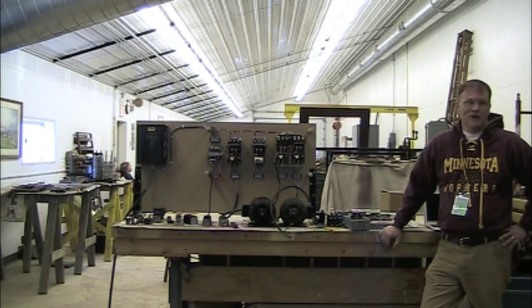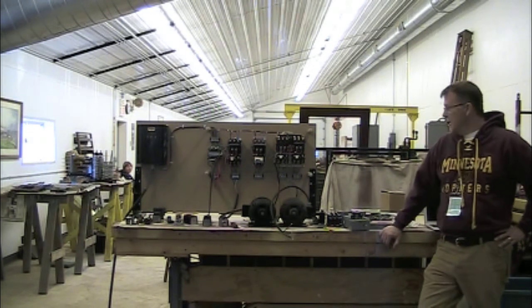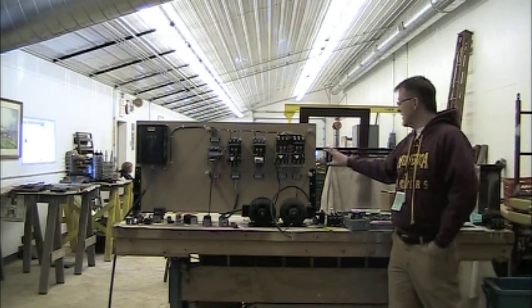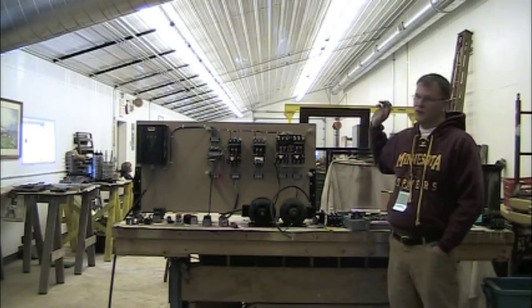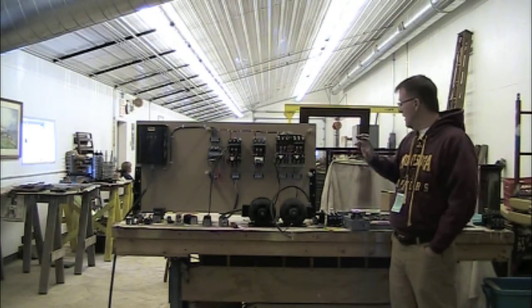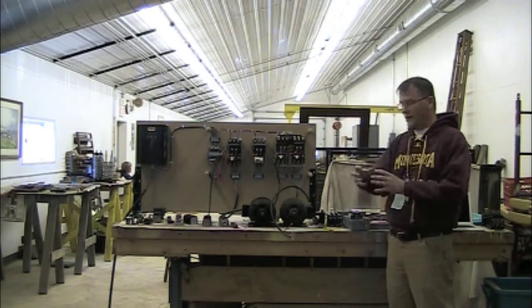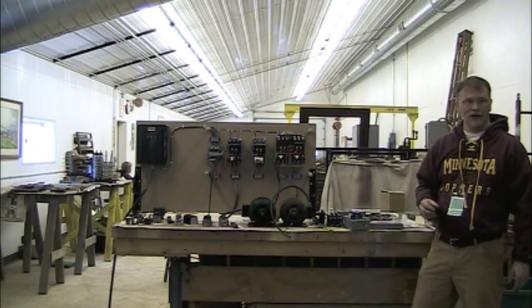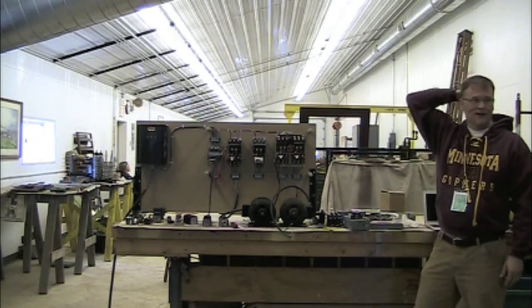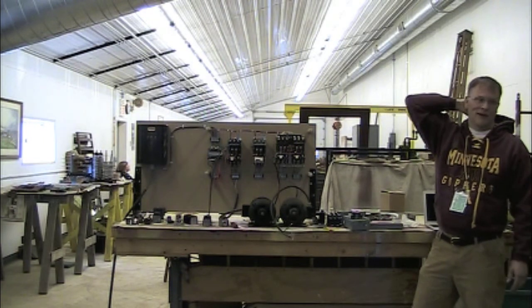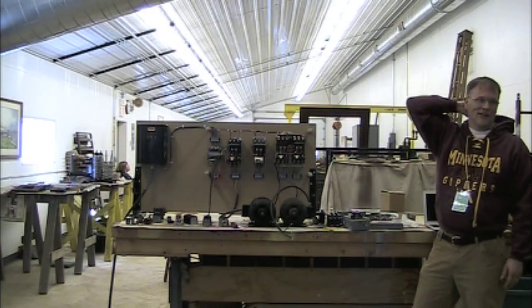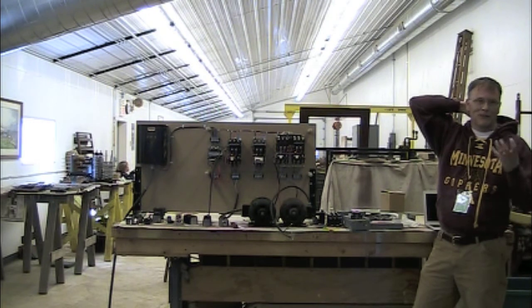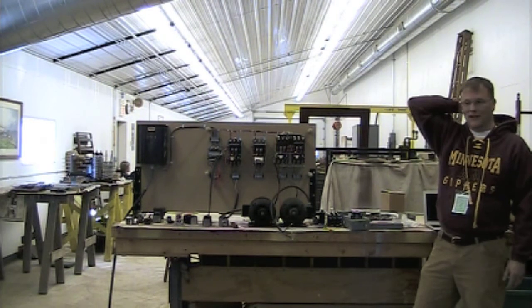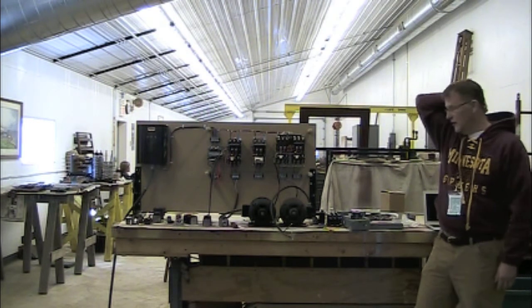I mean, that's typical of the NEMA ones. It's all modular, the contacts are all replaceable, the coils, all the pieces like I showed, it's all components that just bolt together. The IEC ones are pretty much fail and throwaway. They're not designed to have anything done to them. They're just all potted together, and they're not really designed for the same duty cycles.